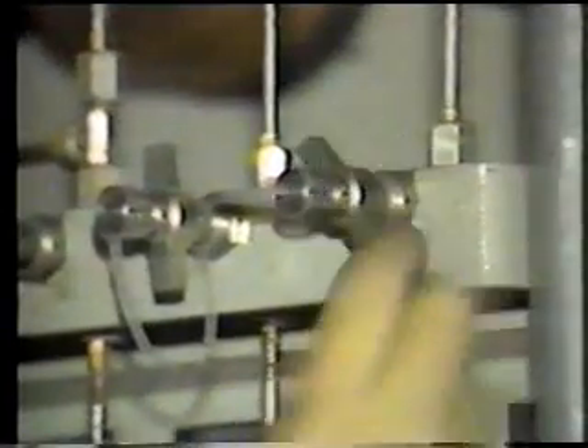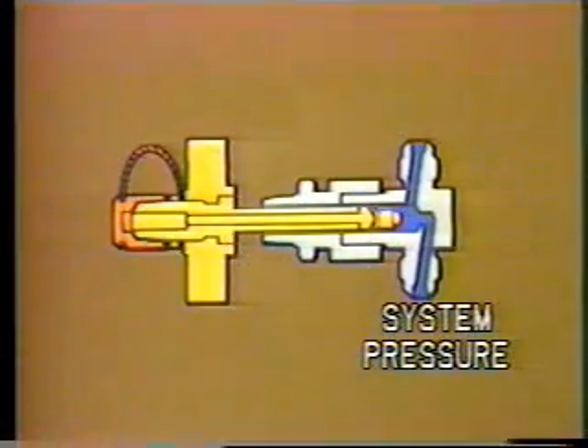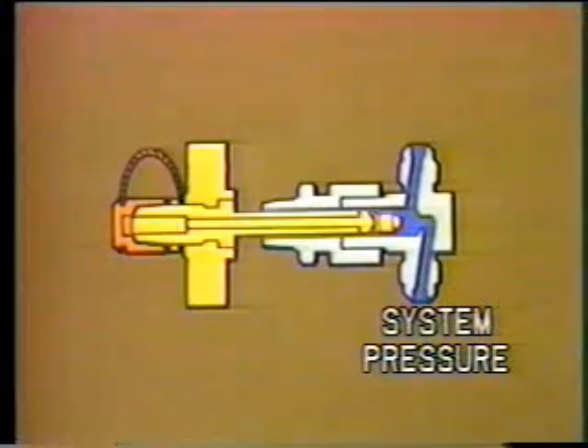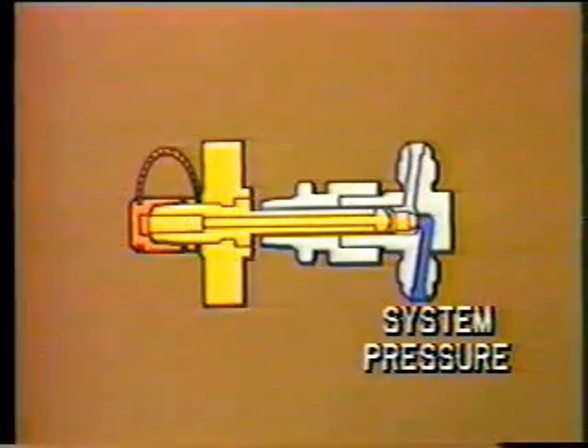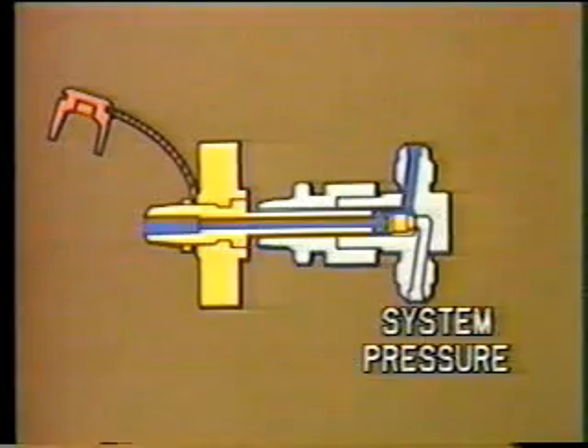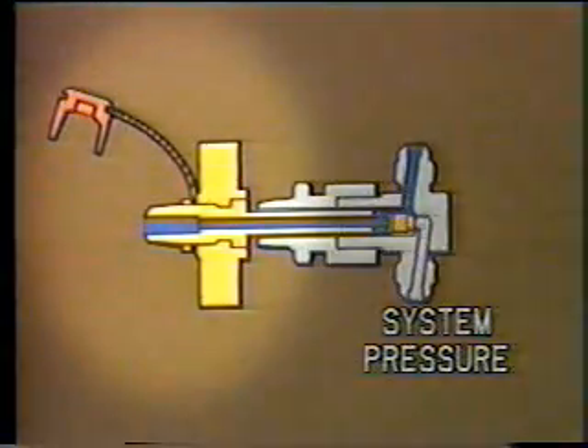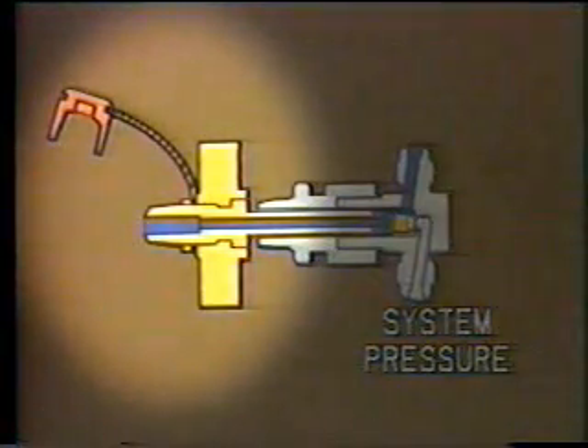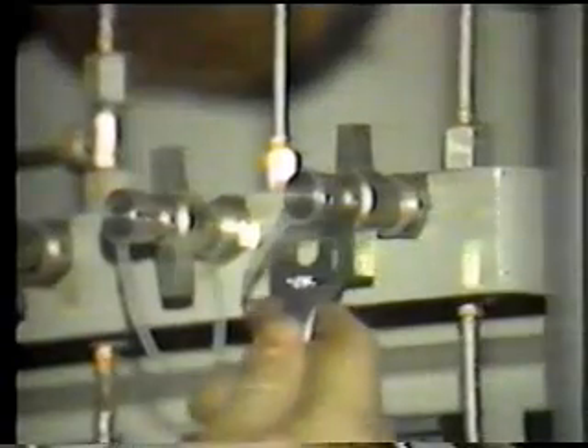First, close the manual shut-off bleed and instrumentation valve, located at the rear of the control console. Note, when using an external pressure source, the valve must be in the closed position. Warning: be careful when removing the test connection cap in the next step. Pressure trapped in the connection can cause personal injury. Slowly remove the test connection cap.